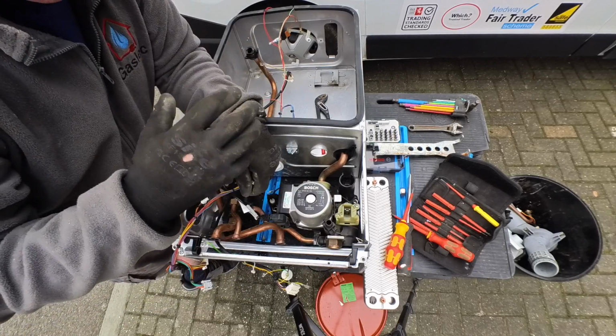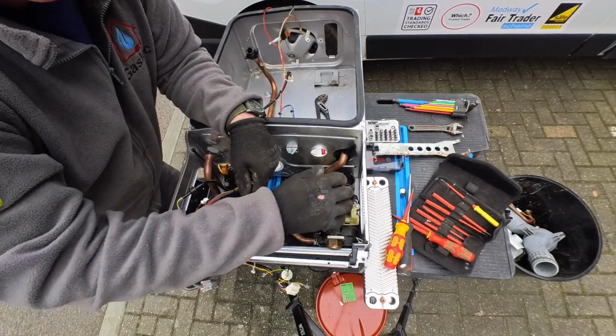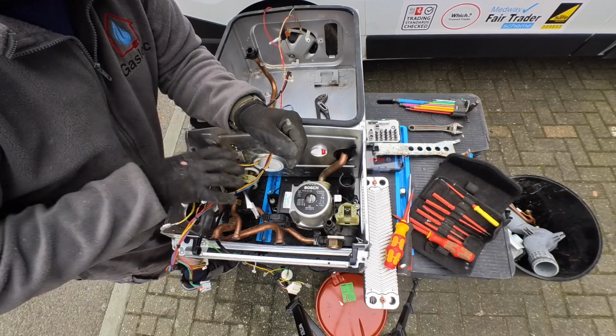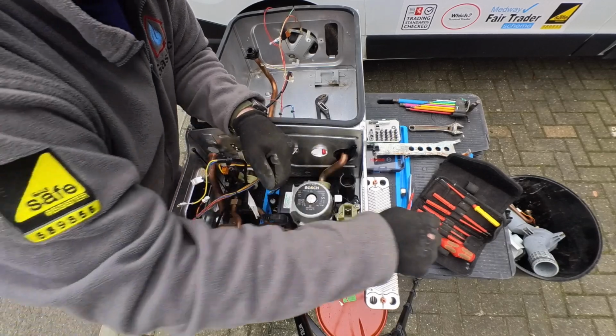The diverting for heating and hot water is done on the return, not on the flow. Some boilers have it on the flow side, but this one has it on the return side.